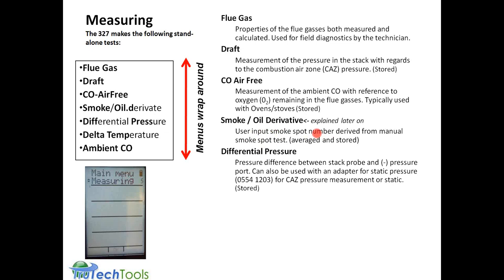Differential pressure is a pressure measure between the stack probe and the pressure port, those two ports at the bottom. And as I mentioned before, there's also an adapter for static pressure for doing differential or combustion air zone or static pressure measurements, say, if you wanted to determine static pressure in a ductwork or a static pressure differential over anything in a ductwork, through a heat exchanger, over an air conditioning coil.